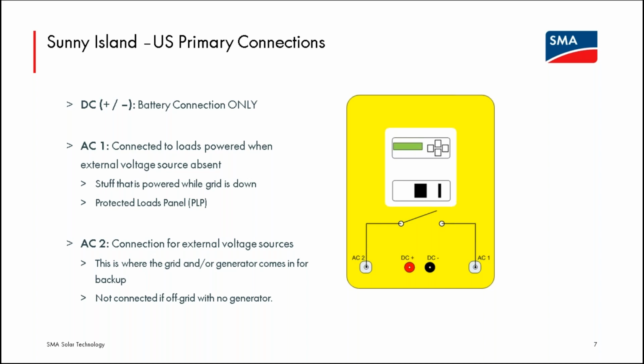The AC2 terminals would be, quote unquote, upstream of the Sunny Island. That would be where an external voltage source, such as a generator or the utility grid, connects. If the Sunny Island is used in battery backup mode, grid power coming to the AC2 terminals can flow across the transfer relay that we show as open in this diagram and go to the AC1 terminals. So in battery backup mode, the Sunny Island will allow grid power to pass to the loads. It will pull off what it needs to charge the batteries, but it doesn't have to use battery power to power those loads. It can lean on the grid until the grid might fail.